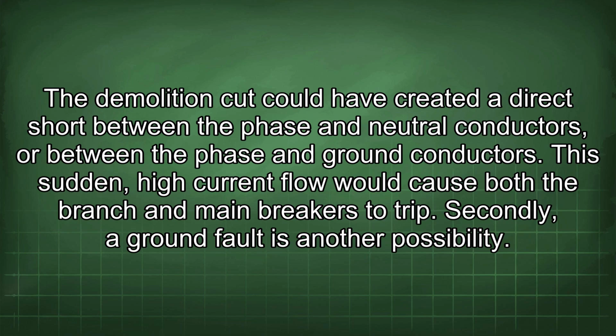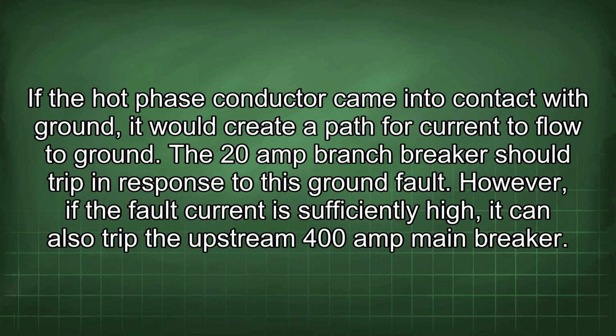Secondly, a ground fault is another possibility. If the hot phase conductor came into contact with ground, it would create a path for current to flow to ground. The 20-amp branch breaker should trip in response to this ground fault. However, if the fault current is sufficiently high, it can also trip the upstream 400-amp main breaker.